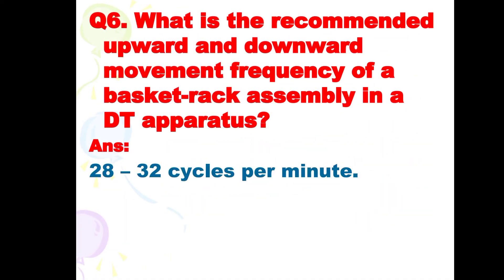Next is: what is the recommended upward and downward movement frequency of a basket rack assembly in a DT apparatus? The answer is: 28 to 32 cycles per minute.